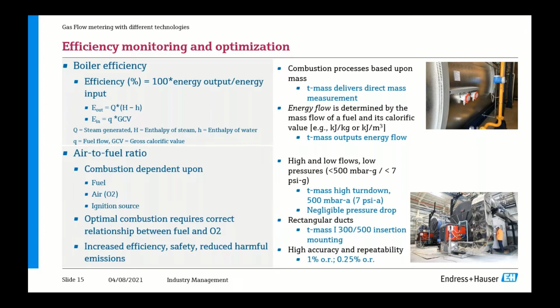Also provided by the software of the T-mass device is a so-called calorific value. The calorific value is based upon the type of natural gas used, so based upon the composition of the gas. The software of T-mass will provide this calorific value based upon the gas that is configured in its software. This can be used for the calculation of energy flow, which again is used in the boiler efficiency calculation.